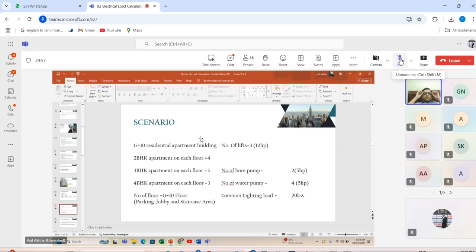Basically, this is a scenario I created for a ground plus 10 residential apartment building, in which the number of lifts is 3, with a rating of 10 HP. Let's suppose 2 BHK apartments on each floor is 4, 3 BHK apartments on each floor is 3, and 4 BHK apartments on each floor is 3. The number of bore pumps I have selected is 2, with a rating of 5 HP, and the number of water pumps is 4, with 5 HP. The residential building is a ground plus 10 floor building.